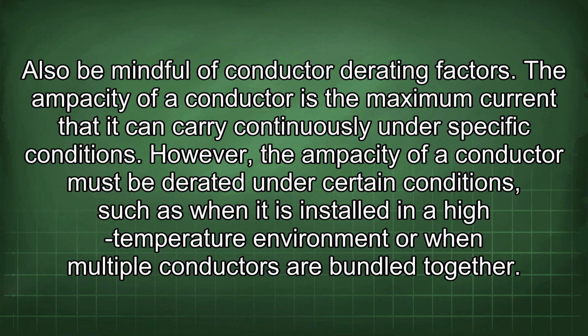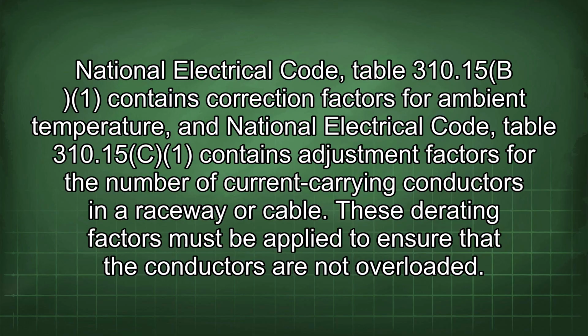The ampacity of a conductor is the maximum current that it can carry continuously under specific conditions. However, the ampacity of a conductor must be derated under certain conditions, such as when it is installed in a high-temperature environment or when multiple conductors are bundled together. National Electrical Code Table 310.15(B)(1) contains correction factors for ambient temperature, and National Electrical Code Table 310.15(C)(1) contains adjustment factors for the number of current-carrying conductors in a raceway or cable. These derating factors must be applied to ensure that the conductors are not overloaded.